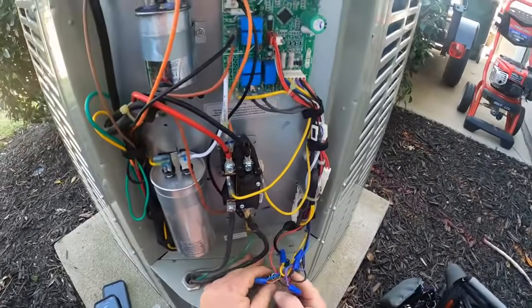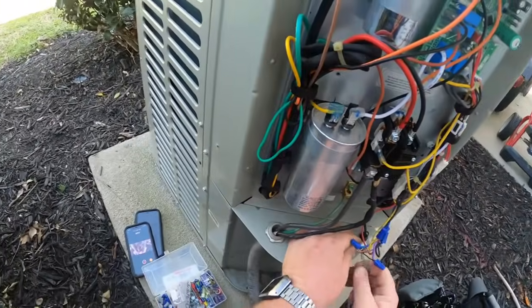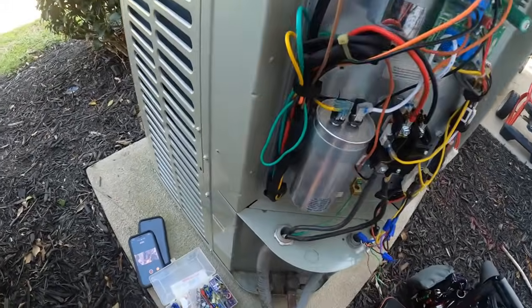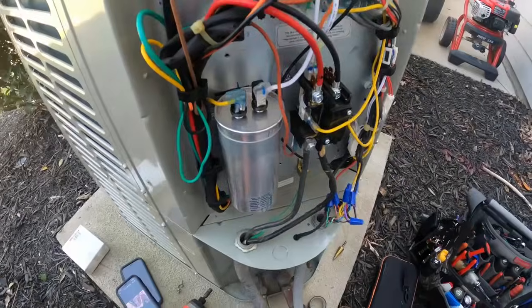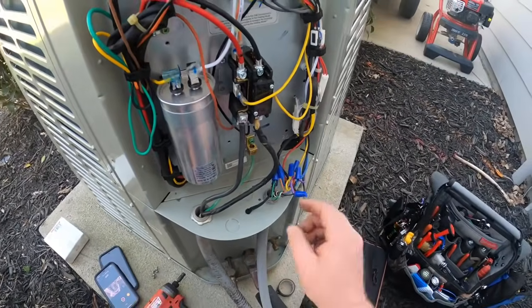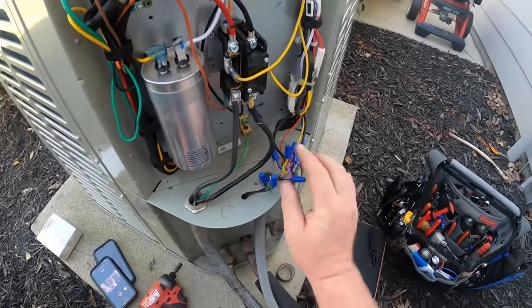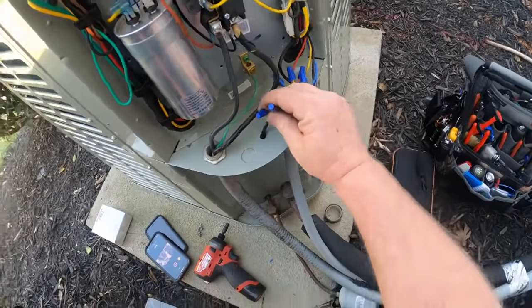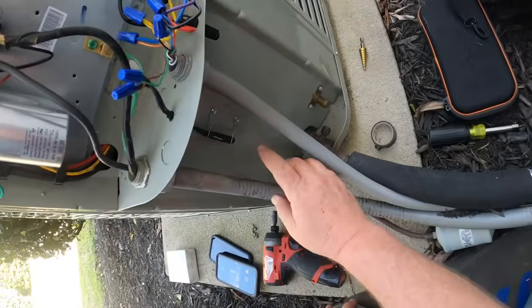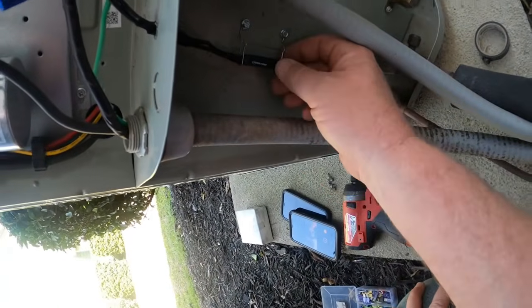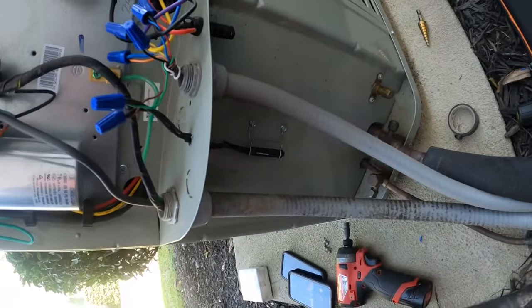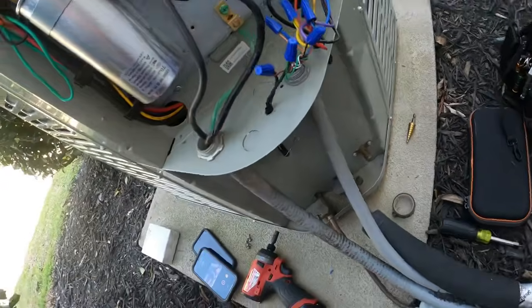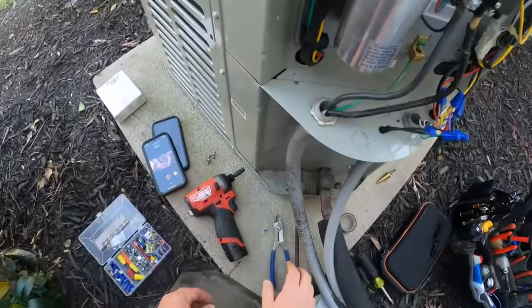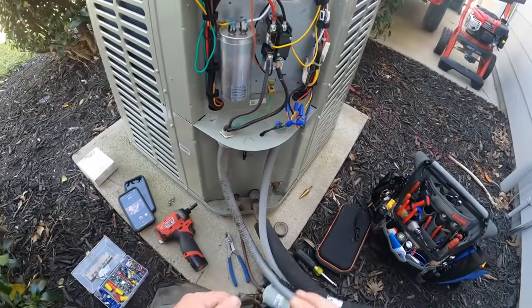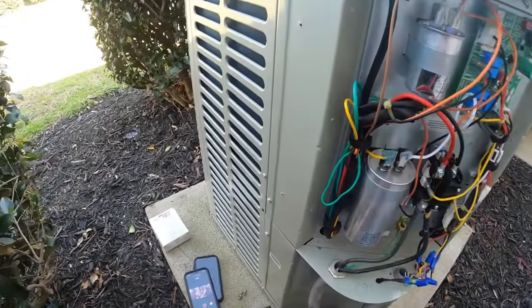I need to figure out where I want to bring this sensor in at and tie it in. Okay, so what you see I've done is got everything wired up out here about the way it should be, and I've added this right there, Honeywell outdoor temperature sensor, to tie back into that zone board so I can go in there and set my lockouts between the heat pump and the furnace.